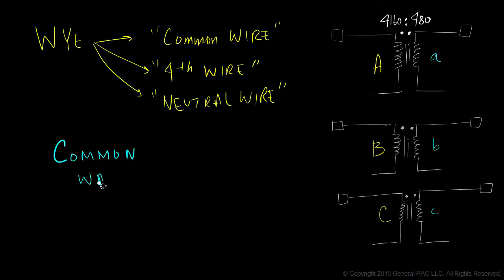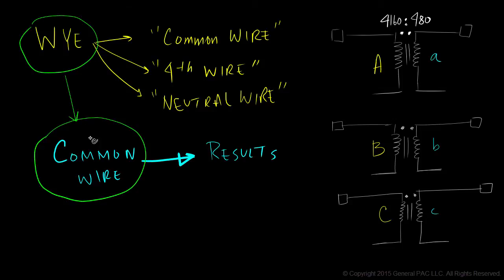The Y-connected transformer is distinguished by a common wire, which is also referred to as a fourth wire or a neutral wire. This common wire can be connected in various ways to achieve very specific results. The Y connection is almost always found with a common wire connected to the non-polarity side of the windings. This is how we'll configure our transformer in this example.